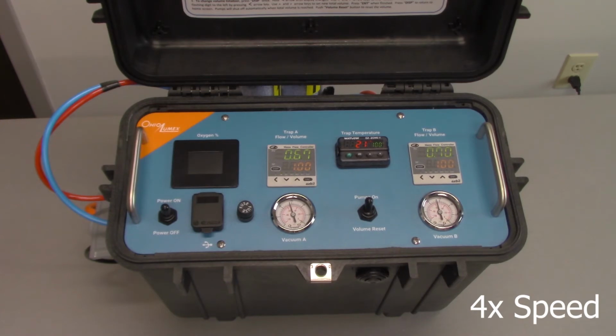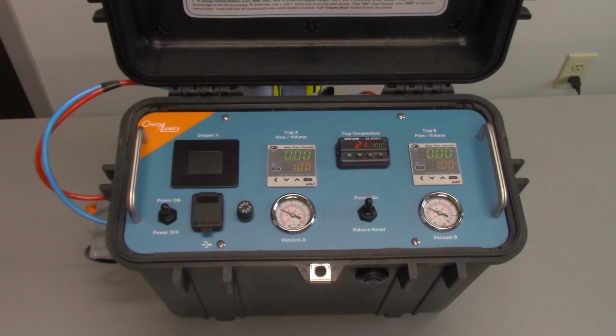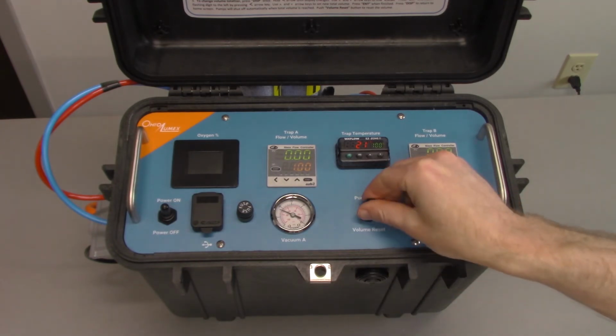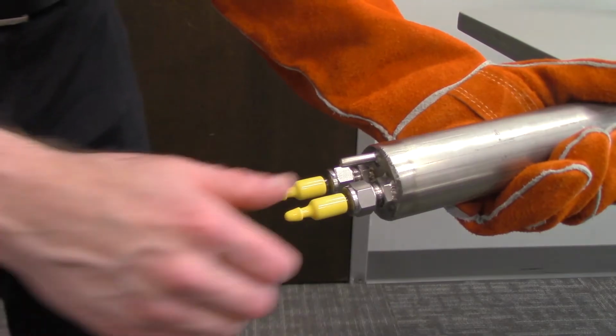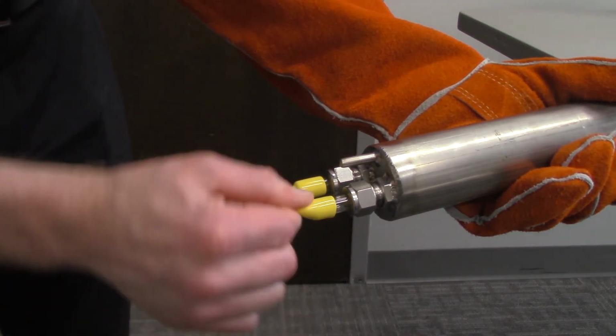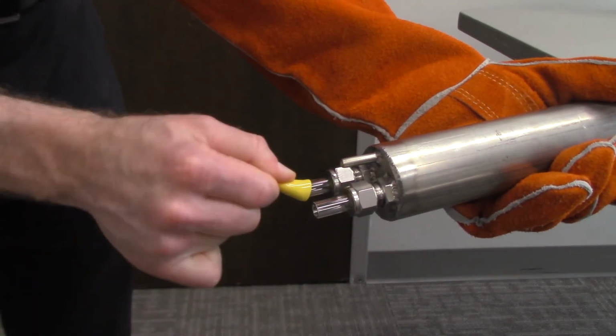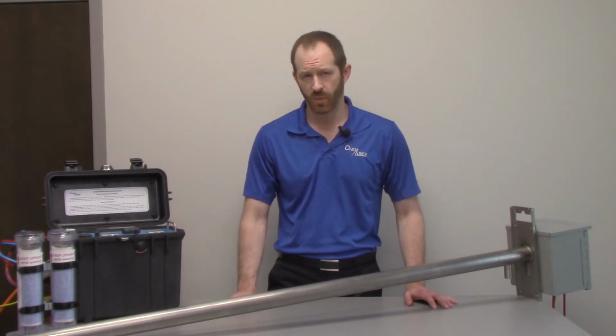Once you see the flow rate is stable at 0, you've passed your leak check. Technically, the allowable leak rate is less than or equal to 4% of the set flow rate, but with this sampling system, you should be able to hit 0 every time. Once you've passed the leak check, you can turn the pumps off and slowly remove the trap caps. Now you're ready to insert the probe and start sampling.